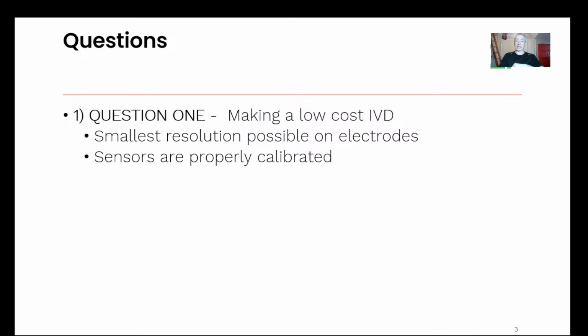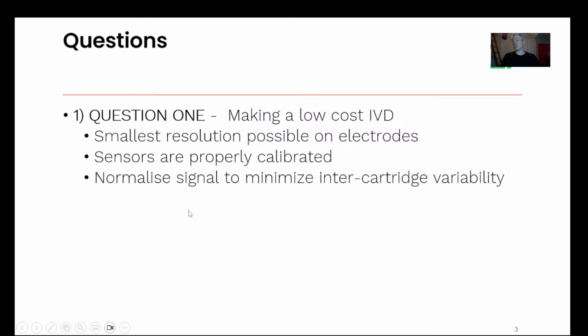Question here, sensors are properly calibrated. This is really a manufacturing issue. And it's something that you really either solve by using materials from people like Zimmer and Peacock, or you unfortunately have to get enough funding that you can put a quality system in place to make sure that you don't have issues of sensors not being calibrated. It's interesting actually because they mentioned that electrodes might get chipped off. So I have a suspicion, I've never spoken to this person directly, but I have a suspicion that you may have gold on glass. That does tend to chip off a lot. So avoid those gold electrodes on glass if that's what you're using.